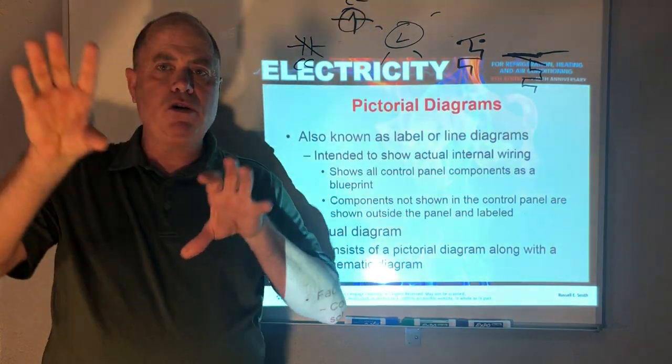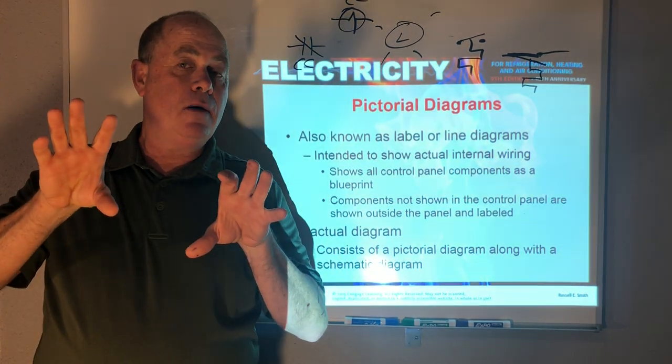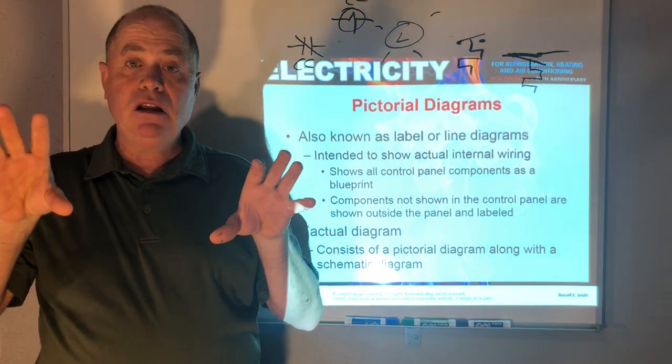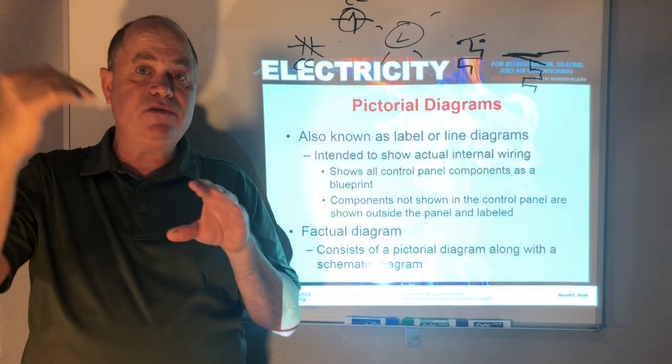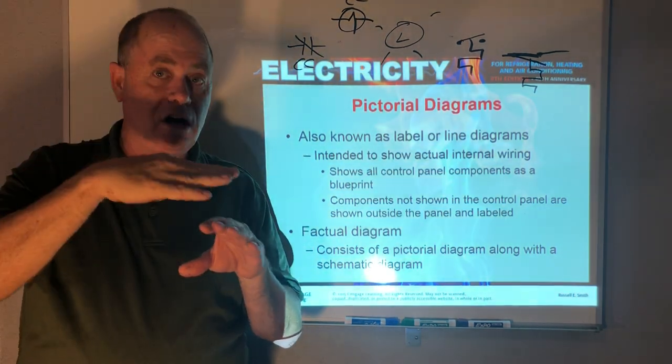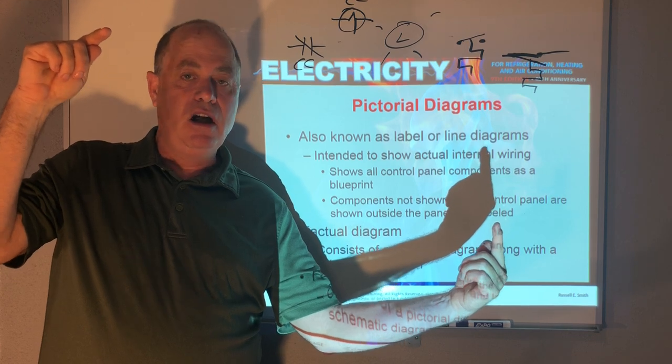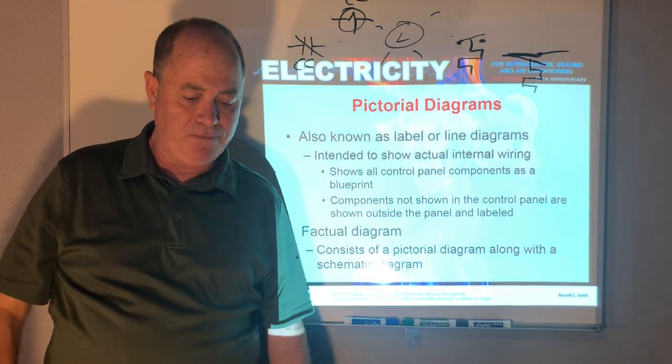Now pictorial diagrams is a little different. This kind of shows you where the components are located in a panel. And it also will kind of tell you different wire numbers or colors and where they do actually terminate. So that if over here you have wire 51, then you can see the other end is over here on this component wire 51.